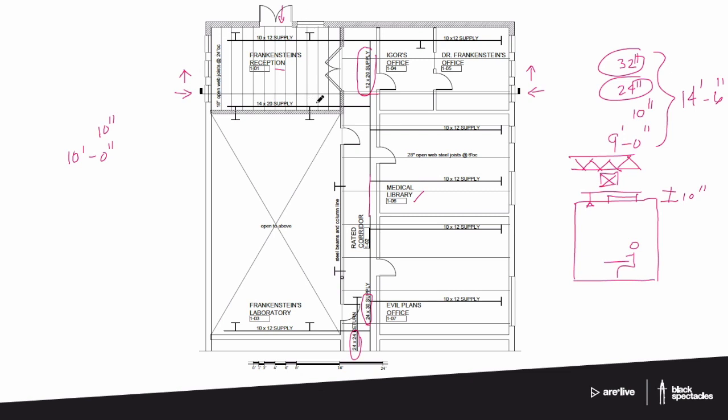It's only one little area. We don't really have to accommodate all of this other ductwork, which is in a different ceiling heighted area. It's a different set of relationships. It really only has to accommodate the biggest one in its own area, which in this case is 14 inches. So we've got a 1'2" here, and then its own structure, which is 18 inches plus the 4 inches for the slab. So we're at 22 inches, which is 1 foot 10 inches.